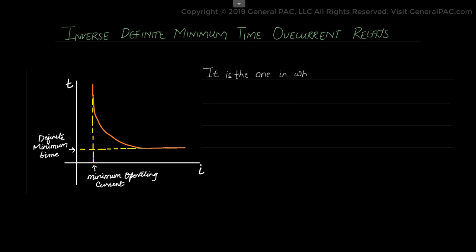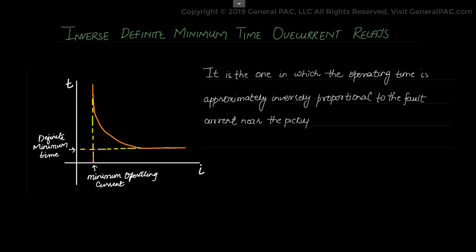The third category is called the inverse definite minimum time, the IDMT overcurrent relay, which is the one in which the operating time is approximately inversely proportional to the fault current near pickup value and then becomes constant above the pickup value of the relay.